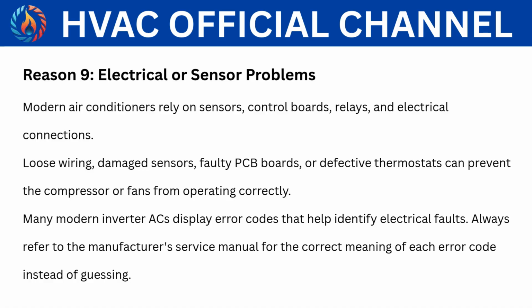Reason 9. Electrical or sensor problems. Modern air conditioners rely on sensors, control boards, relays, and electrical connections. Loose wiring, damaged sensors, faulty PCB boards, or defective thermostats can prevent the compressor or fans from operating correctly. Many modern inverter ACs display error codes that help identify electrical faults. Always refer to the manufacturer's service manual for the correct meaning of each error code instead of guessing.